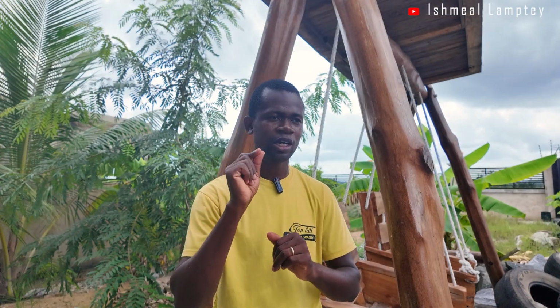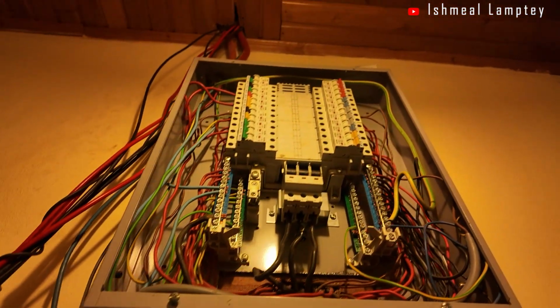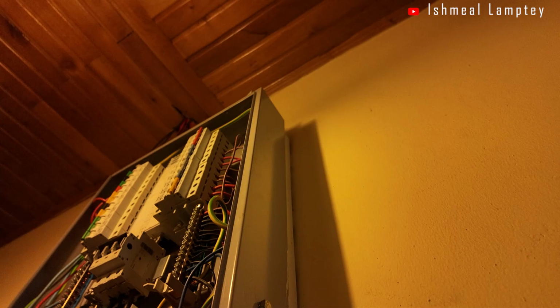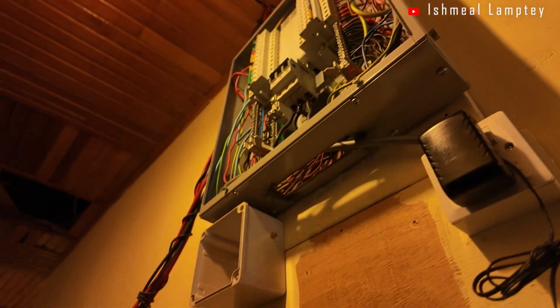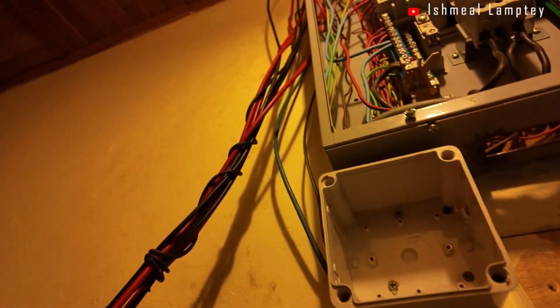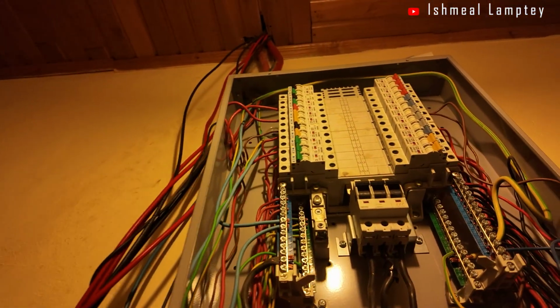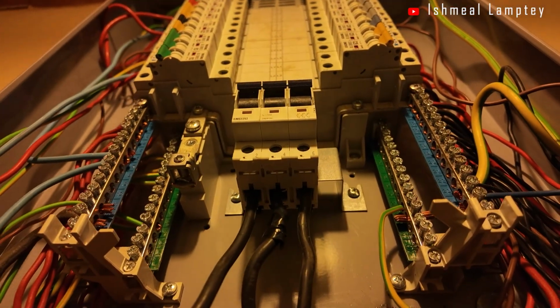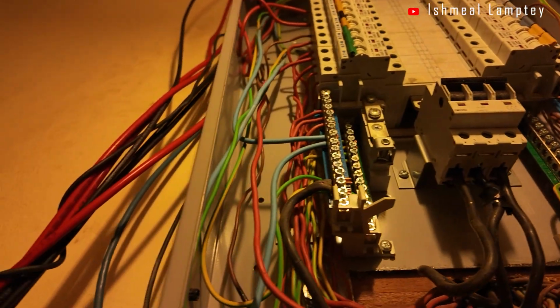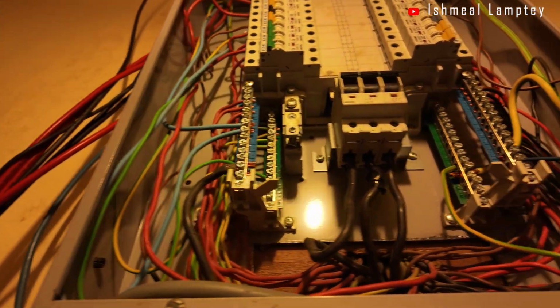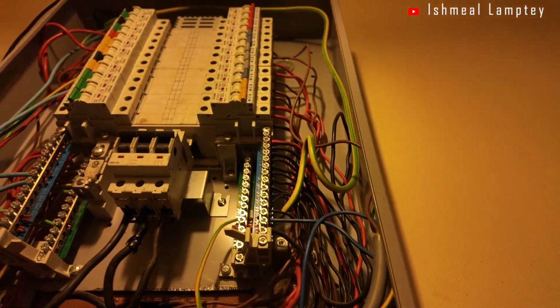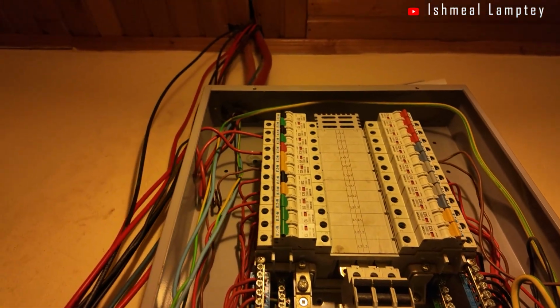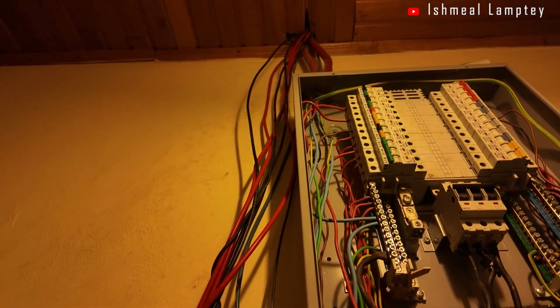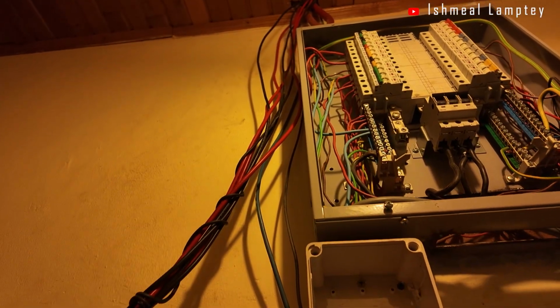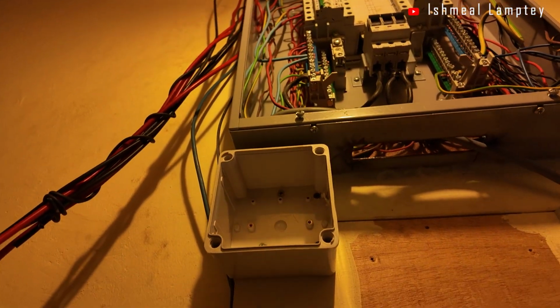One of the breakers actually was giving wrong feed to the inverter, which was preventing power from the inverter from going into the house. Yes, and this was not our fault, this was actually the wiring which was done in the house. So we had to take time. So this system, which would have taken us a maximum of 2 days, took us 3 days to figure out everything. So we took our time to trace all the breakers, what the purposes that they were serving, where they were going, and all that.